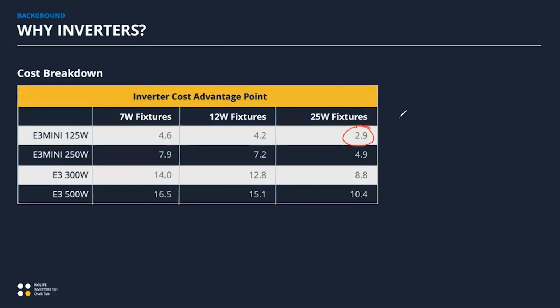If you look at this number, assuming our building has 25 watt fixtures and we have 3 or more of them as part of the emergency system, that means the E3 Mini 125 watt is going to be less expensive. If you have 2 or less, then the emergency drivers are going to be less expensive and have the benefit.